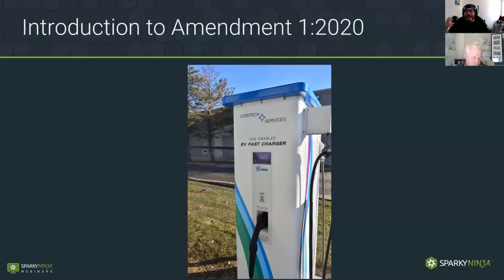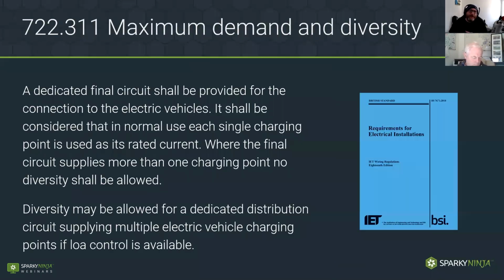With regards to the maximum demand area, it used to say in 722.311, in the 18th edition, right at the bottom here, that diversity may be allowed for dedicated distribution circuits supplying multiple electric vehicle charging points if load control is available. We did mention this in a recent maximum demand webinar. That was the assumption that if we were going to put lots of electric vehicle charging points into one infrastructure, we could maybe have load control. So if we pull on one and then we pull on the other, it would dampen down that demand.